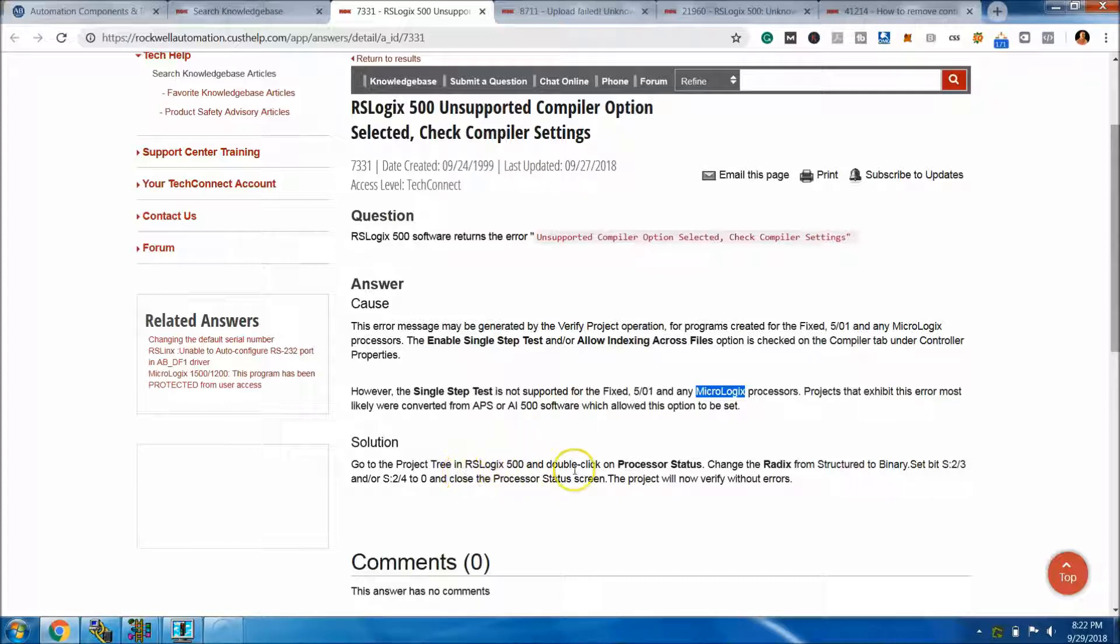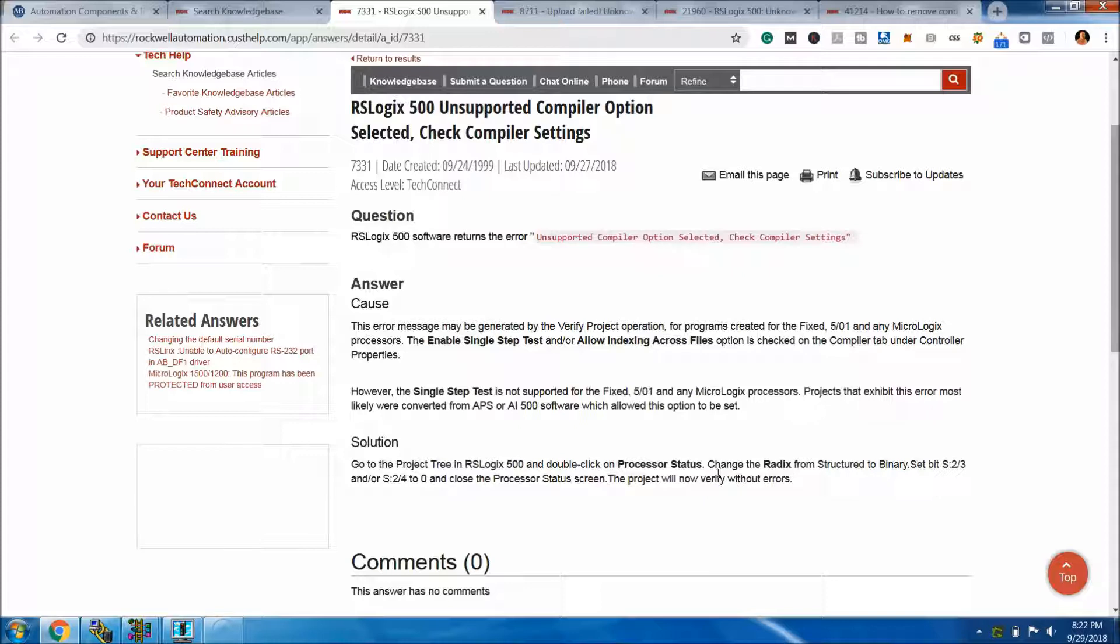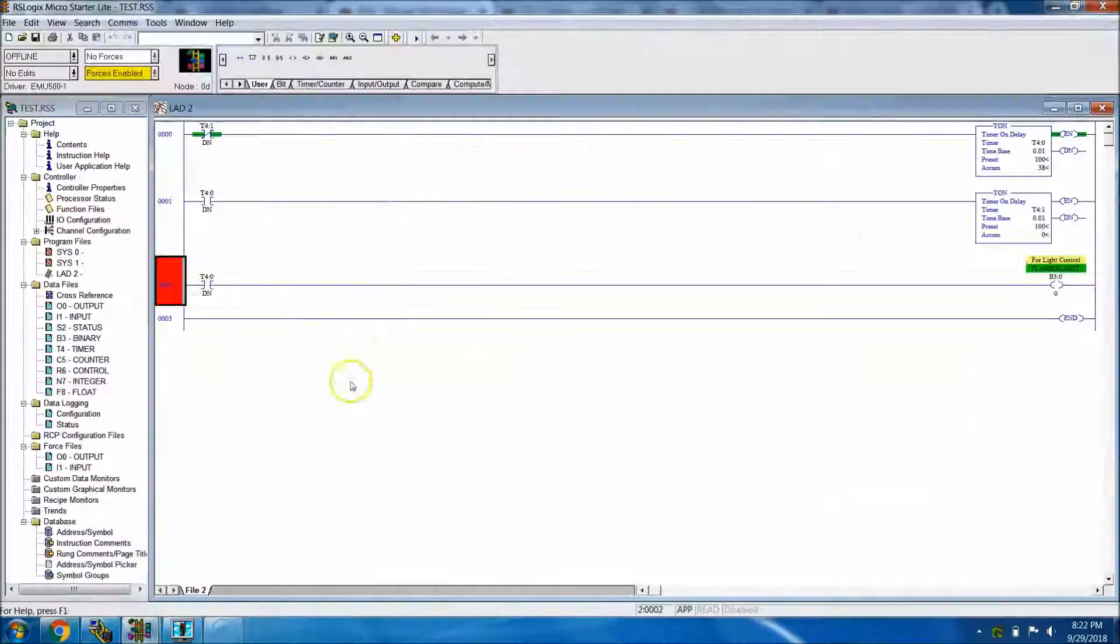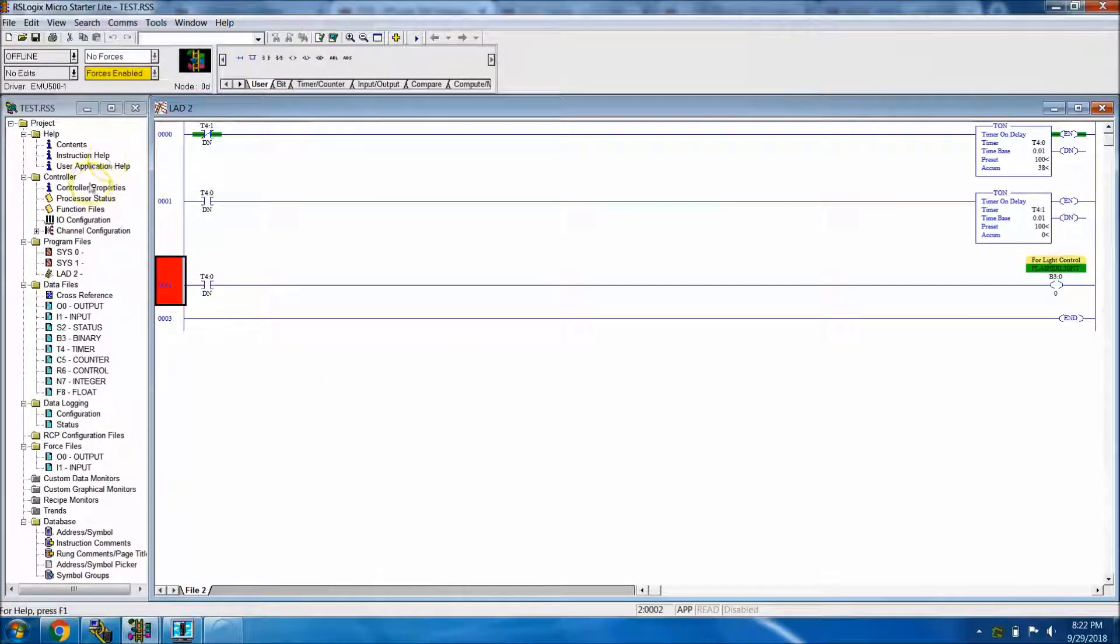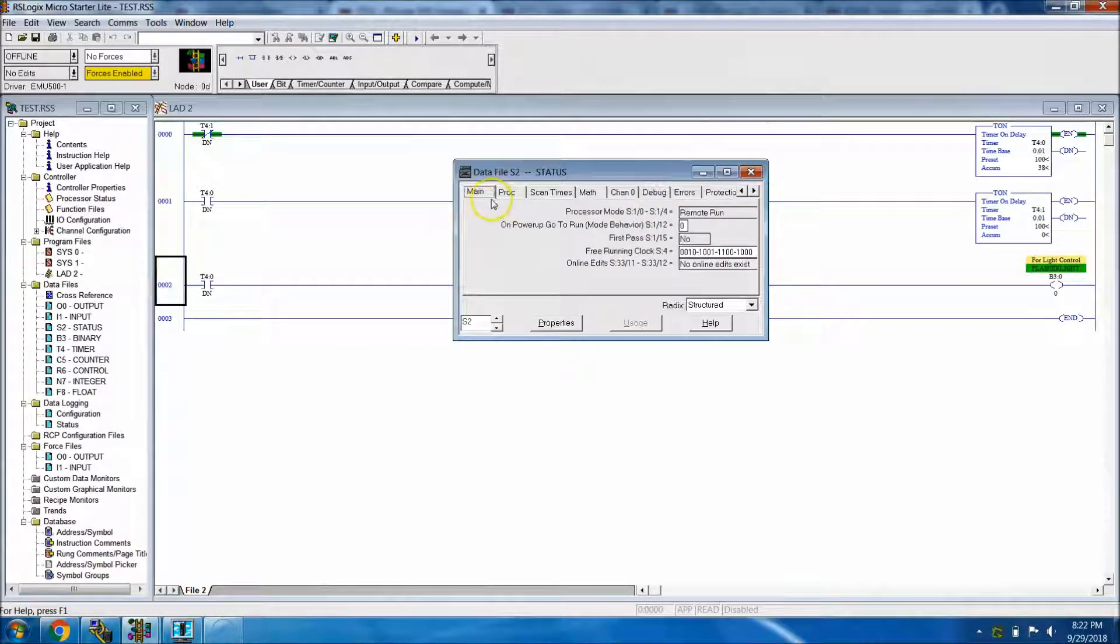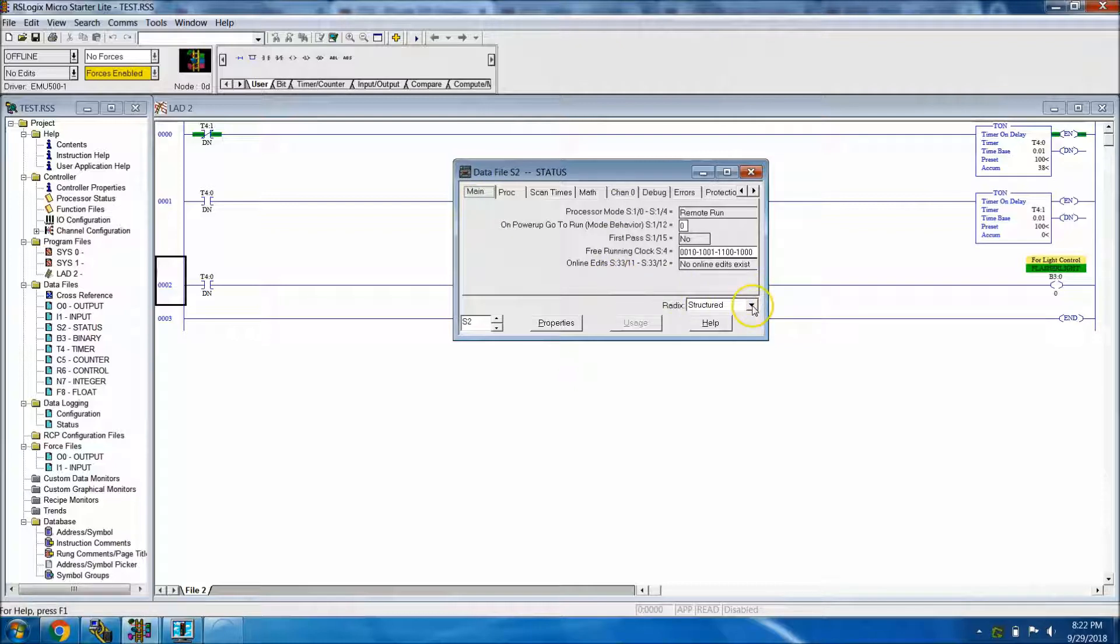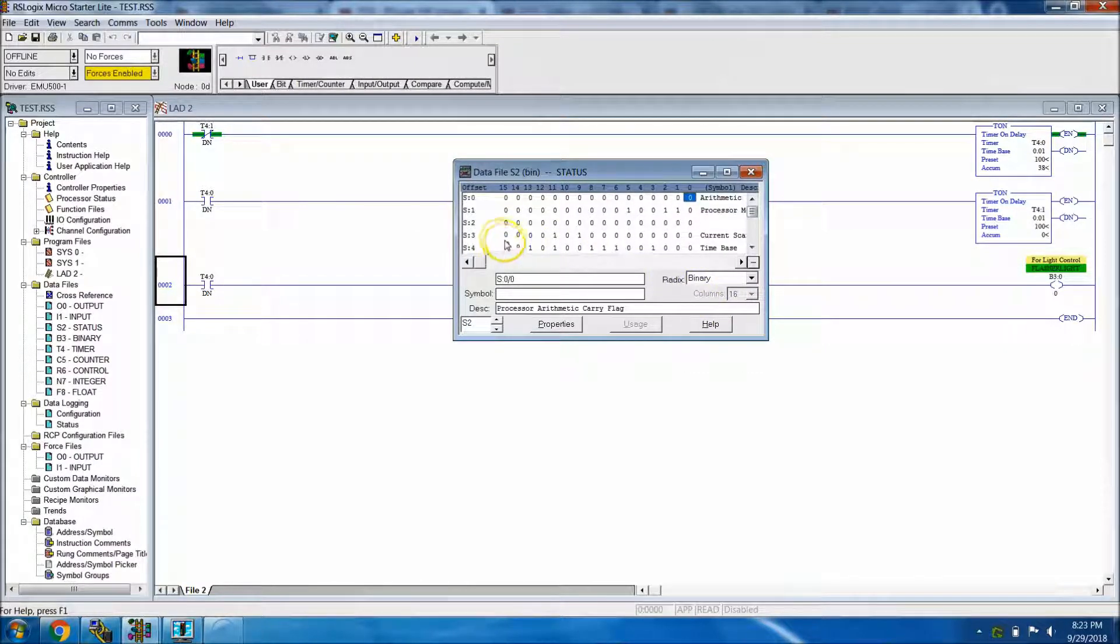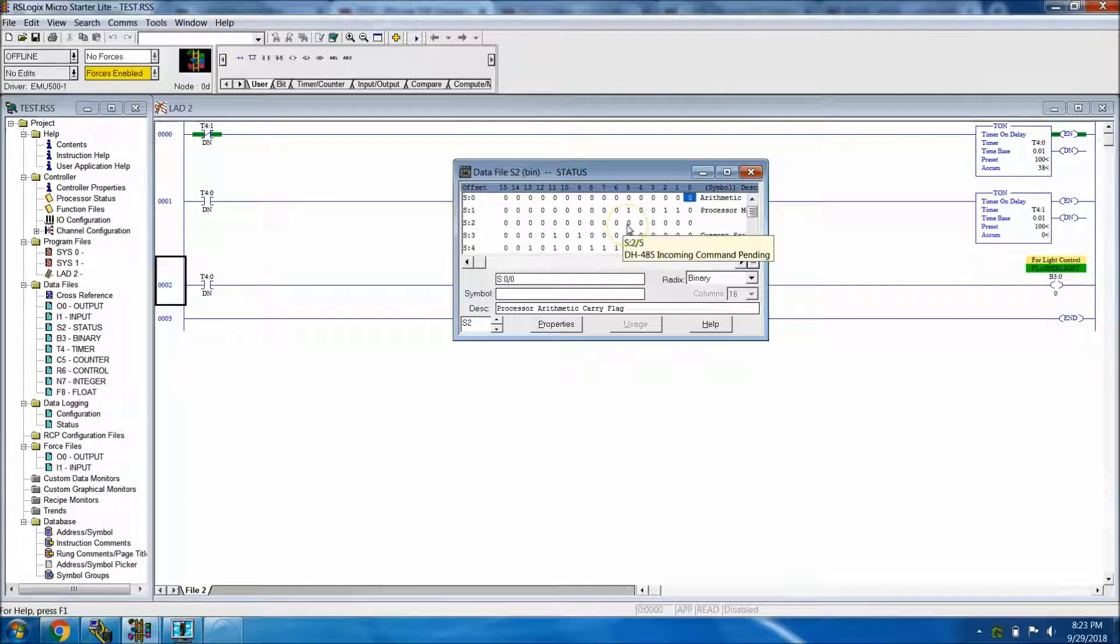The solution is telling you to go to the processor status and verify a few things. At this point, how do you do that? I'm going to show you exactly how to do that. For one, you need to change the radix from structure to binary. What that means is basically your data type. You're going to go over to processor status, stay in main right here, and then you're going to change the radix right here from structure to binary.